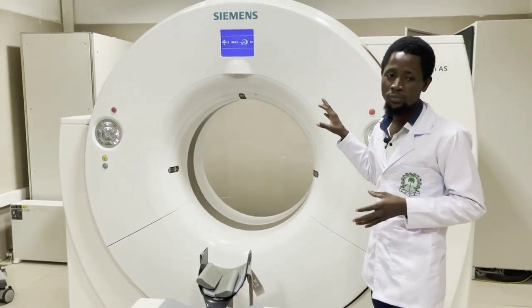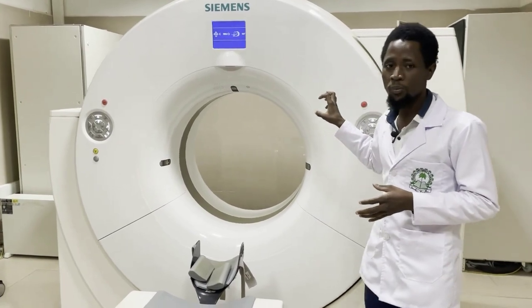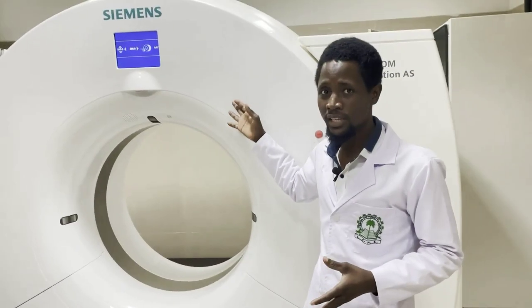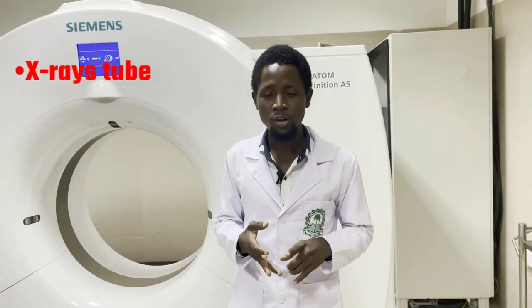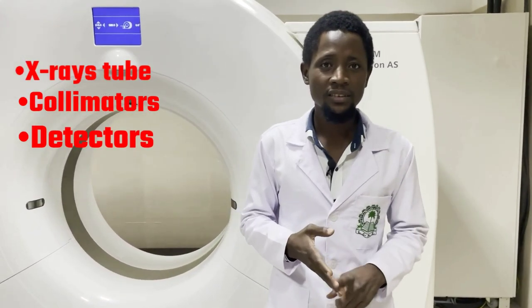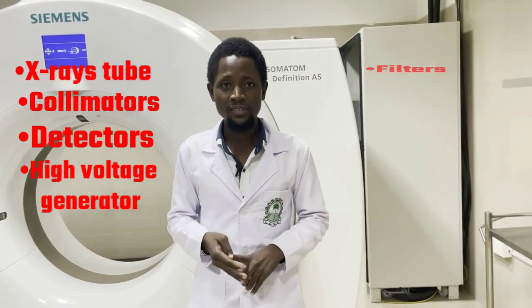There is also the internal component of the anterior side of the gantry. Anteriorly and internally, the gantry is mounted with different components which include: X-ray tube, collimators, detectors, high voltage supply, filters, and data acquisition system. The X-ray tube is used to generate X-rays.